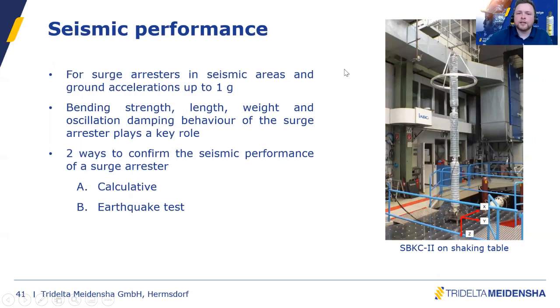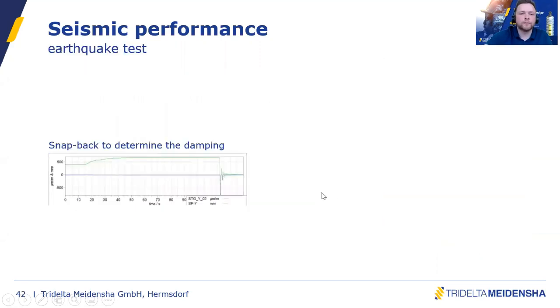One mechanical consideration is the seismic performance of the surge arrestor when they are installed in areas where earthquakes can occur. And important design parameters are the bending strength of the surge arrestor, as explained, the length and the weight of the surge arrestor, and the damping behavior. And there are actually two ways to confirm the seismic performance of the surge arrestor. One is calculative. We can calculate the mechanical strength under seismic condition. And we can also provide an earthquake test. And on this point, I want to explain a little bit more.